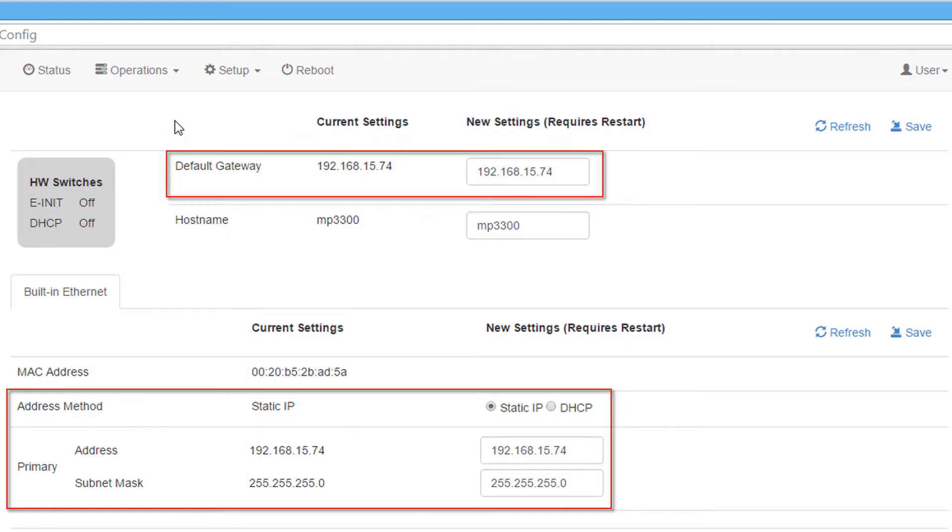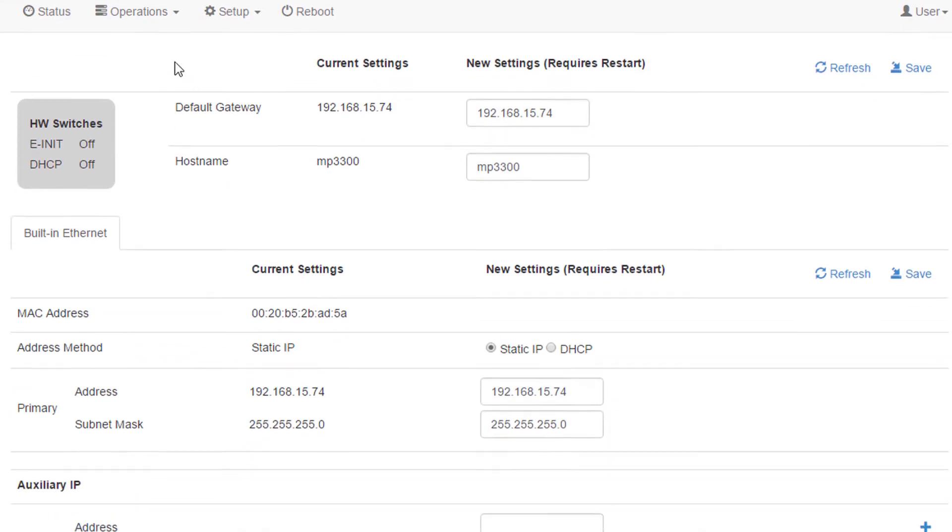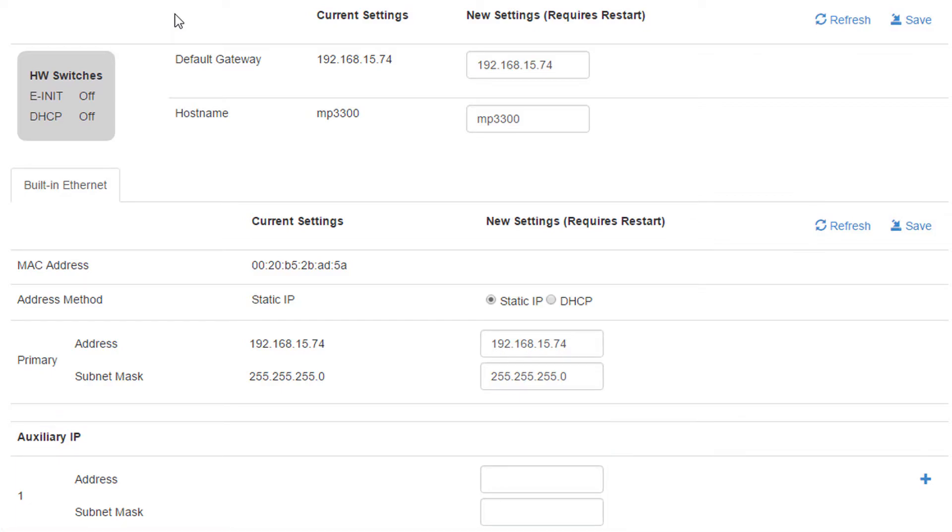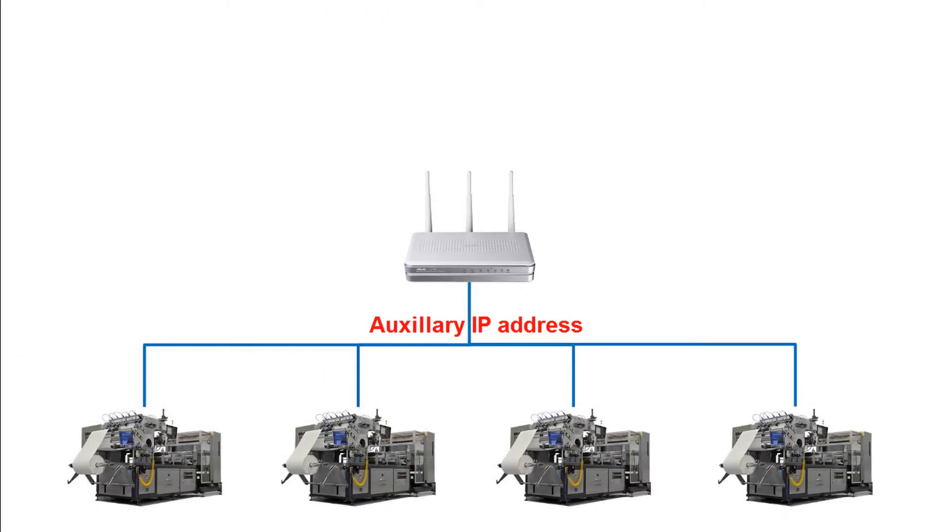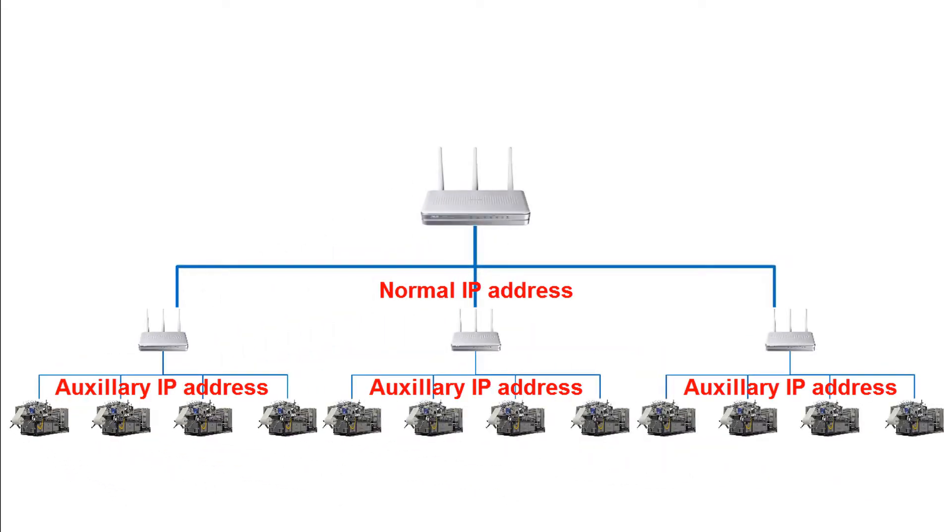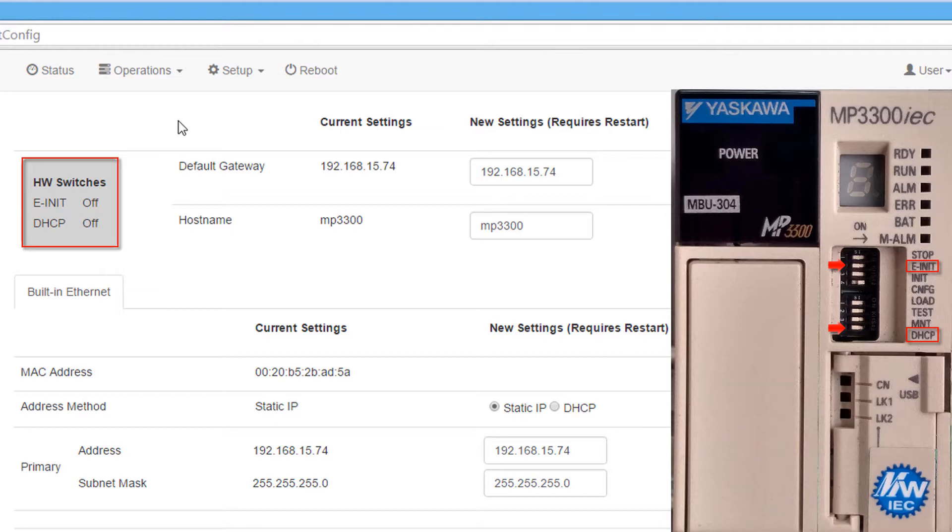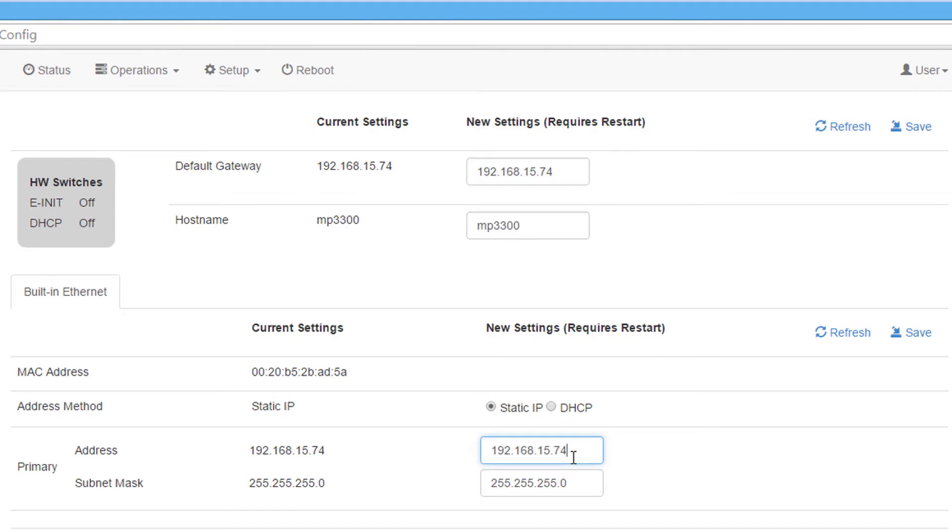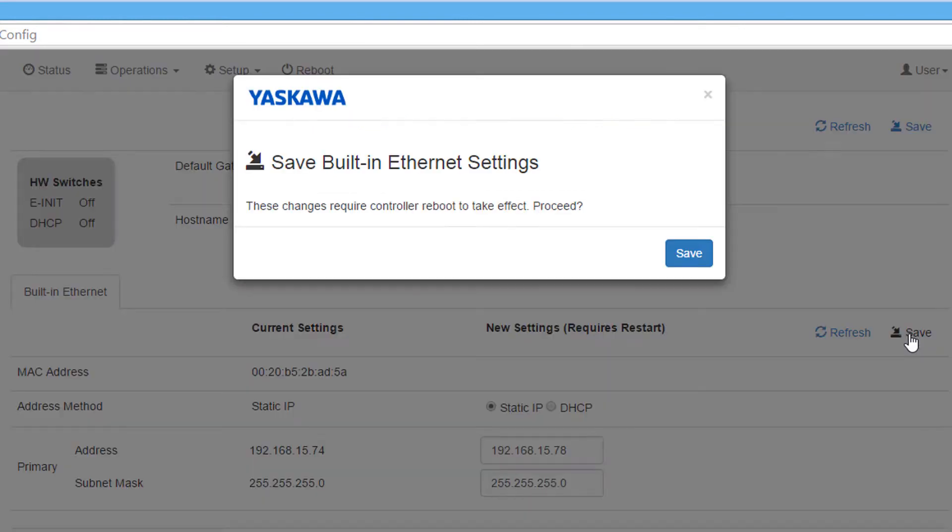The Ethernet config function allows the IP address information and the default gateway information to be changed or modified. In this function, you can also set up an auxiliary IP address. This allows the controller to communicate on two or more networks, for example, the local machine network and the industrial plant network. This screen also shows whether the e-init switch is turned on and whether DHCP mode is enabled. The controller IP address can be changed by inputting a new IP address, selecting save, and rebooting the controller.